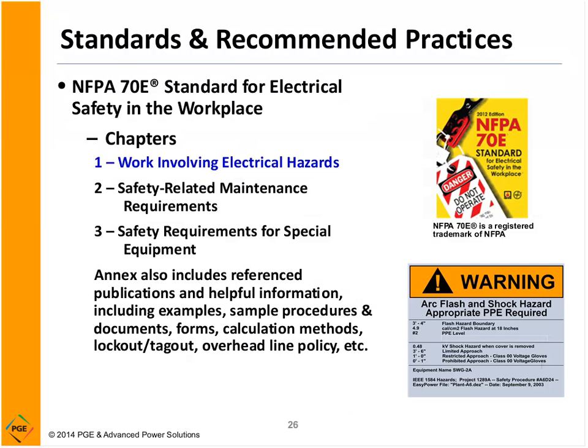We also have NFPA 70E, the standard for electrical safety in the workplace. So chapters 1, 2, and 3, we see we have work involving electrical hazards in chapter 1. We're going to focus there. Chapter 2 gives some very basic safety-related maintenance requirements. And chapter 3 is safety requirements for special equipment, such as adjustable speed drives or battery rooms. The annex also includes reference publications, helpful information, guides, sample procedures, documents, calculation methods for the hazards, risk assessment guidelines and so forth, overhead line policies. And we're looking at the 2012 edition here.